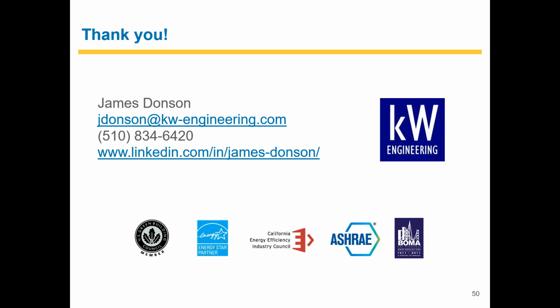It's probably going to have less of an impact on integral LED fixtures that have drivers and LED engines and have been designed from the ground up for LEDs, because you're giving people more space to work with for that driver, so you're getting better components and better heat rejection. It's probably going to be, on the whole, a more robust system than, say, a 2-foot TLED that has to fit a driver in a half-inch tall space 2 feet long, with a price point of $5, $6, $7. At that point, you're having to make a lot of product sacrifices to make that pencil out cost effectively. So you want to keep those things in mind when you're making those changes.